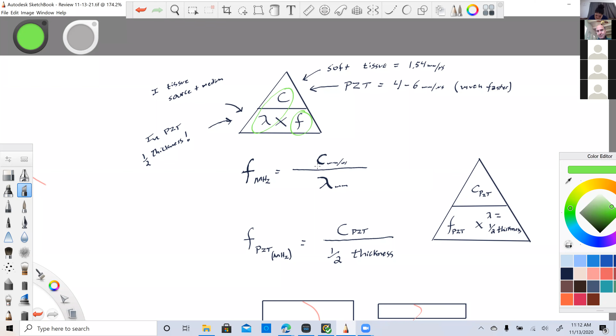Frequency is equal to the speed of sound divided by wavelength, except wavelength is affected primarily or entirely by the thickness of the element. Wavelength is 1/2 times the thickness. And if we draw the sound wave coming out of it, we kind of see why. This is 1/2 a cycle. There's the other half of that same cycle. So this whole span from here to here is one cycle, but half of it at any one time is produced inside the element. And the same thing over here. There's half a cycle, and there's a full cycle. So visually you could see why a thinner transducer will create a higher frequency.